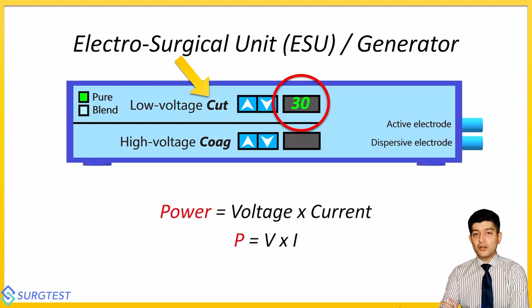Let's specifically talk about cut mode at the 30 watt setting. Remember, it's an alternating current. If I plot a graph of the way the current is moving and what voltage is being delivered, this is the curve you get: a continuous waveform, low voltage current, on pure cut mode. The duty cycle is at 100%, which means that while the alternating current changes direction and passes through zero, the current never actually stops. So delivery of the current is near constant, and the duty cycle stays at 100%.